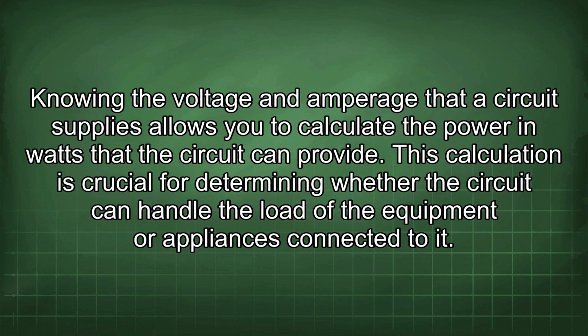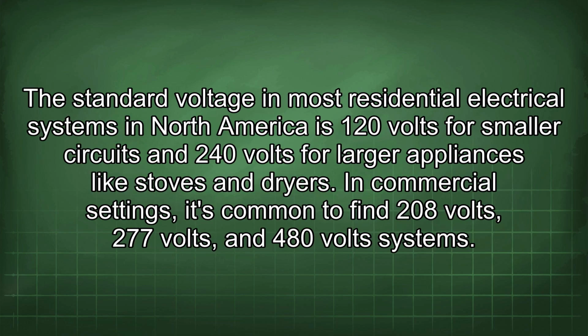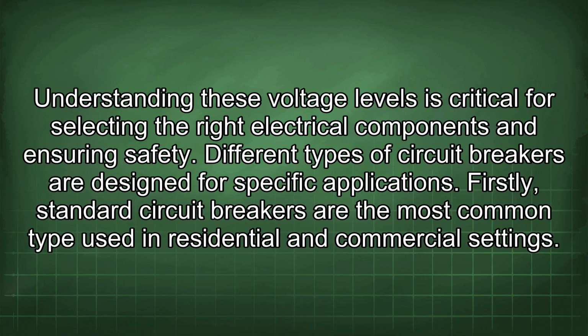Knowing the voltage and amperage that a circuit supplies allows you to calculate the power in watts that the circuit can provide. This calculation is crucial for determining whether the circuit can handle the load of the equipment or appliances connected to it. The standard voltage in most residential electrical systems in North America is 120 volts for smaller circuits and 240 volts for larger appliances like stoves and dryers. In commercial settings, it's common to find 208 volts, 277 volts, and 480 volt systems. Understanding these voltage levels is critical for selecting the right electrical components and ensuring safety.